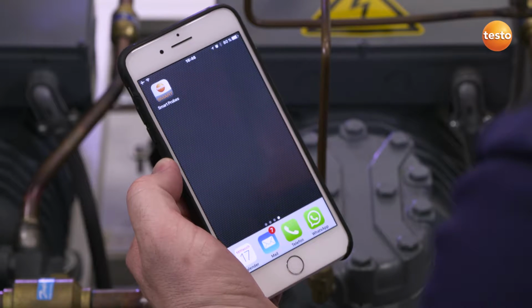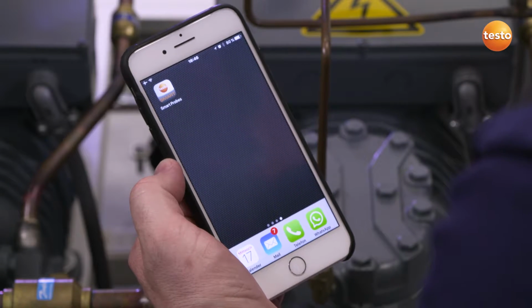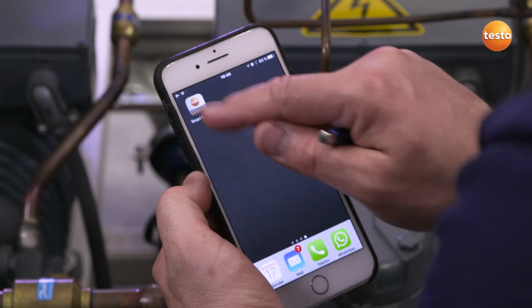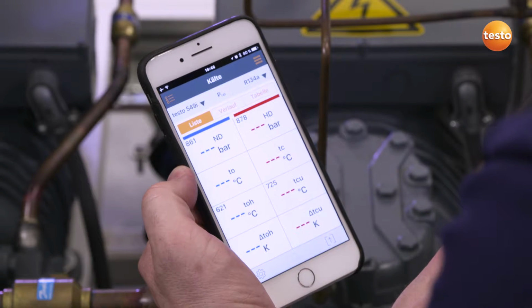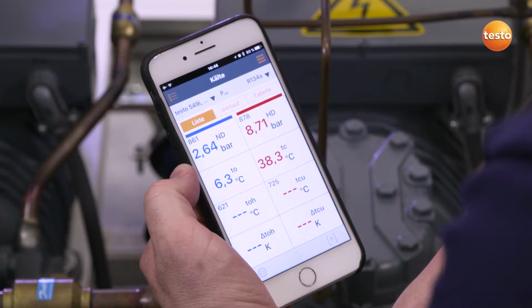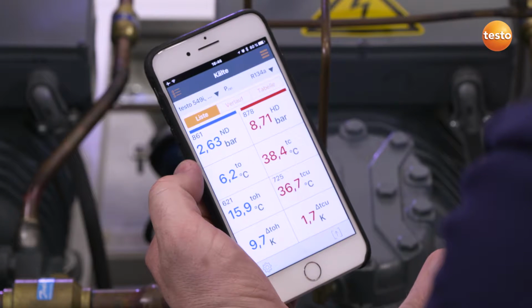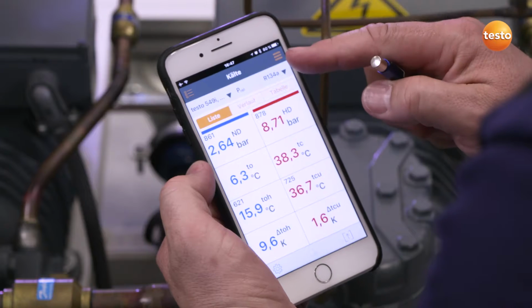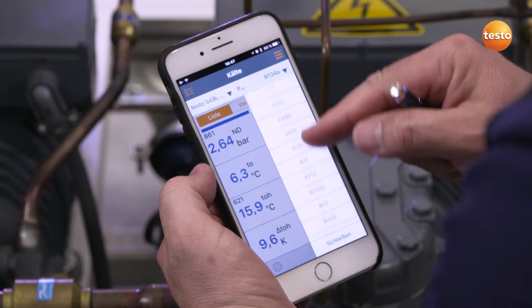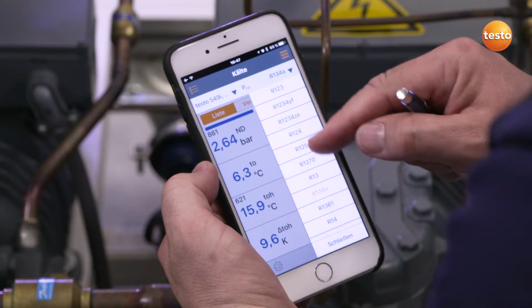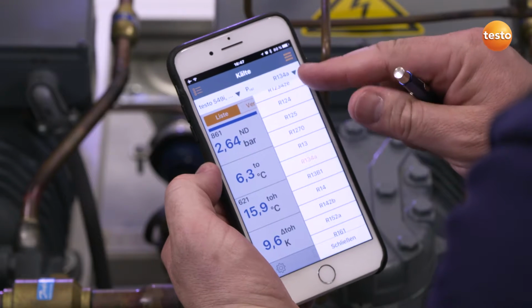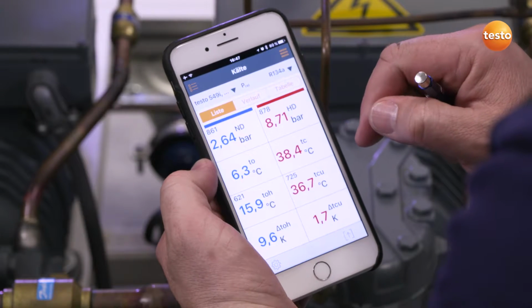Next, I can initiate the smartprobes app, already downloaded for free, and establish a connection. Our 4 sensors are detected by the instrument. The first thing we can do is select the refrigerant that we use in the system. In our case, it's R134a, which has already been preset.